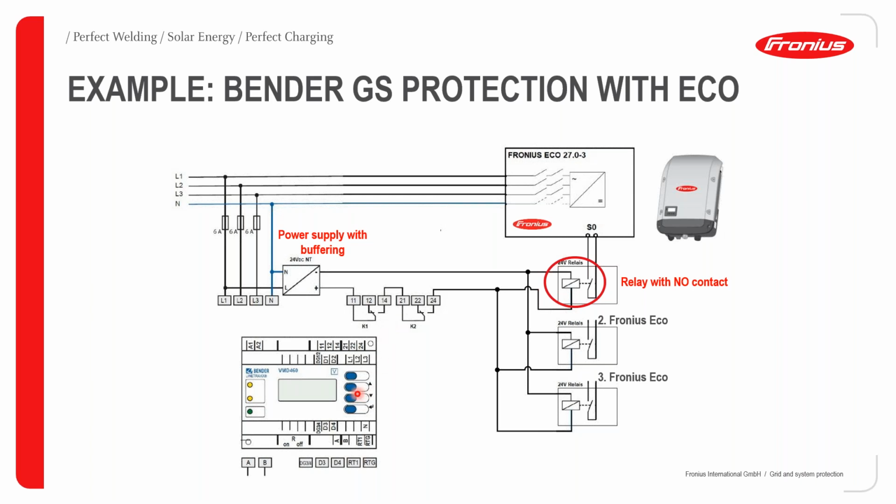Because they should be connected in series, 14 is now looped to 21, which is the contact of the second relay. So 21 is the common, 22 is a normally closed contact, and 24 is a normally open contact. This is now wired to the relay that actuates the S0 switch situated on the Fronius inverter. So this is basically how it is set up in the case where you have multiple inverters to interconnect. Of course, you would need an AC to DC converter to provide power supply and buffering for the relays.